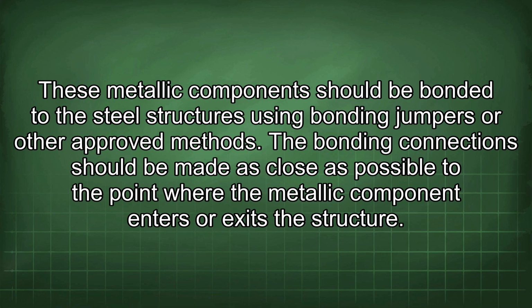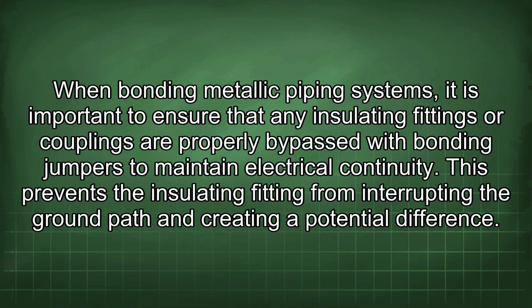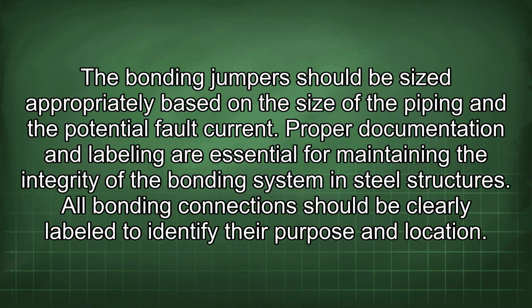When bonding metallic piping systems, it is important to ensure that any insulating fittings or couplings are properly bypassed with bonding jumpers to maintain electrical continuity. This prevents the insulating fitting from interrupting the ground path and creating a potential difference. The bonding jumpers should be sized appropriately based on the size of the piping and the potential fault current.